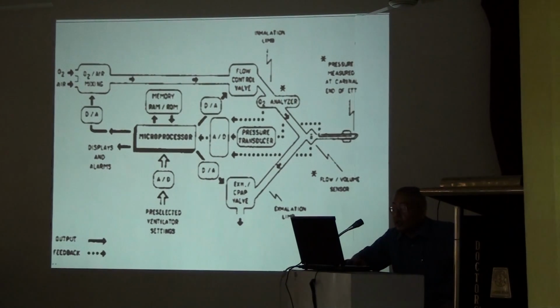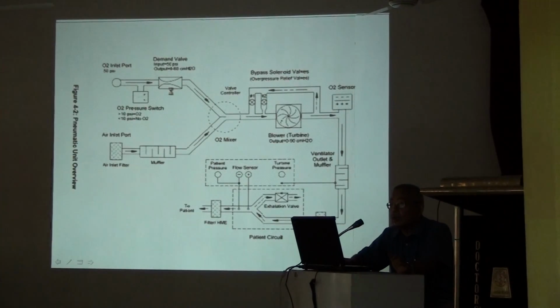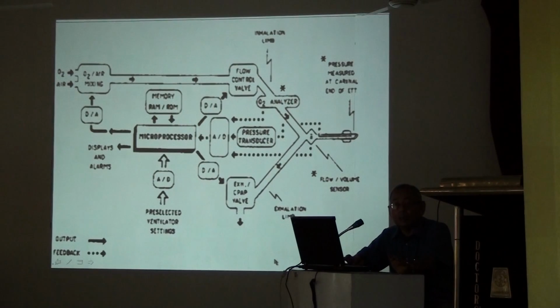Then what will happen? Immediately, if the sensor is here, it will say there is a disconnection because there is no airflow. After a lag period, maybe 5 seconds or 6 seconds, it will display there is no airflow. Means it is leaking somewhere or disconnected. So the exhalation has to be measured here. So now you have understood the basics of delivering air to the patient's lung.